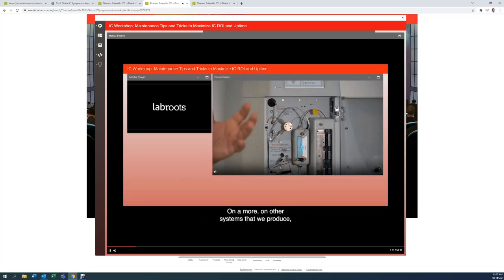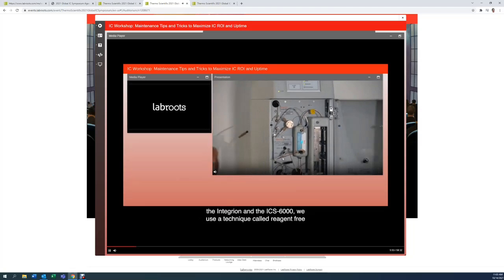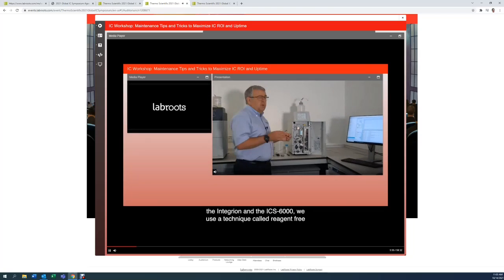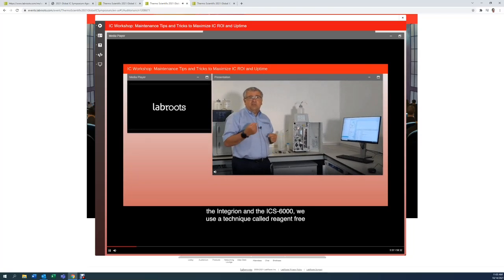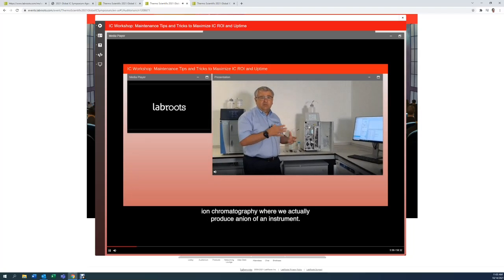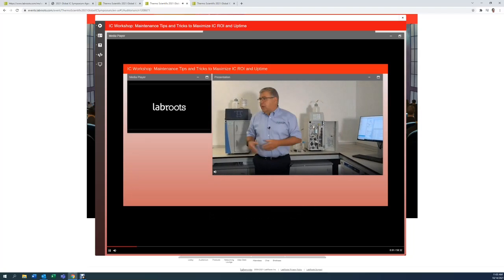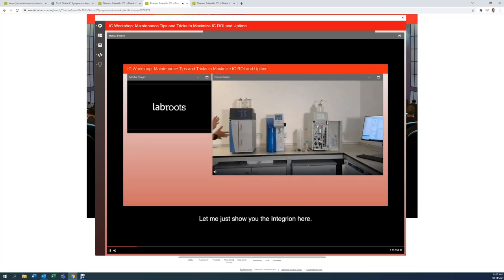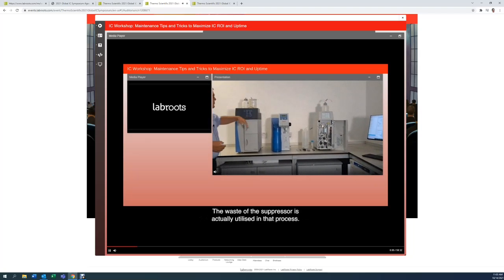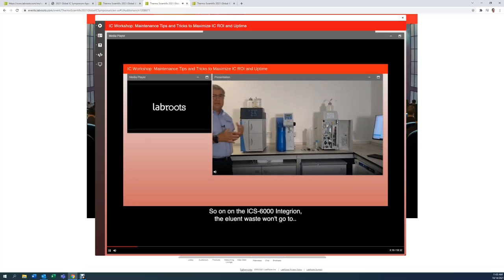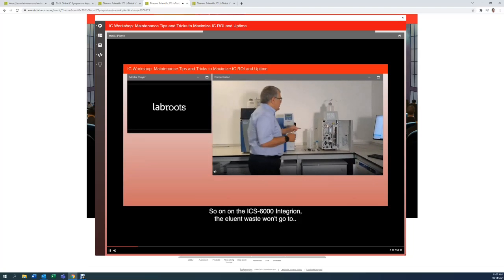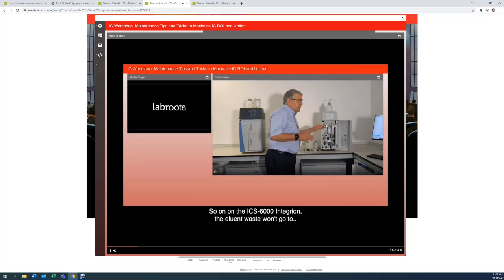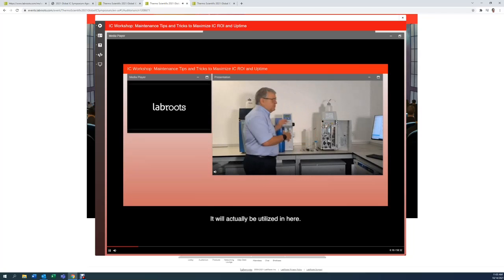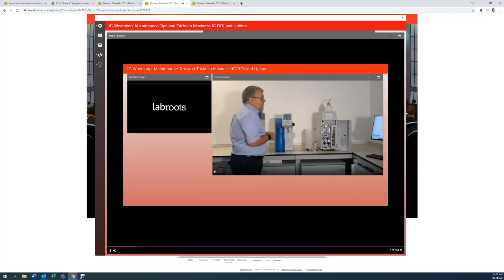On other systems that we produce, the Integrion and the ICS 6000, we use a technique called reagent-free ion chromatography, where we actually produce eluent within the instrument. Let me just show you the Integrion here. The waste of the suppressor is actually utilized in that process. So on the ICS 6000 Integrion, the suppressor waste won't go out to waste. It will actually be utilized in here.